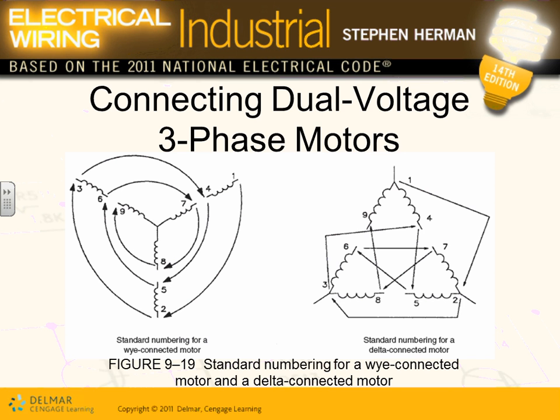Okay, connecting a dual voltage three-phase motor. You guys have done that one, and this is just FYI only. The only thing I want to say is, if you have a delta motor, it comes in 3 pieces. Each piece, can you guys see here, 1, 2, 3, has 3 wires coming out of it. If you have a Y motor, it comes in 4 pieces. 1 piece has 3 wires coming out of it, and the other 2 pieces or coils have 2 wires coming out of each. And we label them clockwise from the top of every coil, as you can see, all the way until you get them all labeled. And I'm not going to do too much on that one.